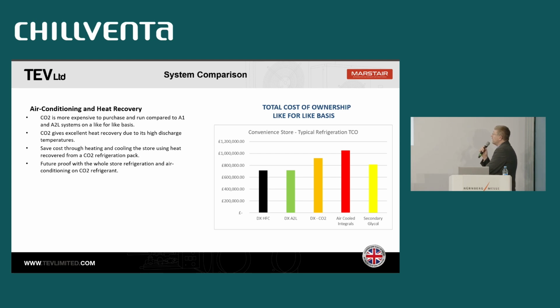So in terms of what I'm talking about, it's air conditioning and heat recovery on CO2. Our cassettes are mostly used with packs for supermarket applications. And generally at the moment, in a direct comparison with normal A1 refrigerants or A2L refrigerants, you tend to find that CO2 is more expensive, purely because of the pressures that you're working with, the cost of the kit and just how complicated it is. So if you can improve the efficiency of the system, and by that I mean recovering the heat for air conditioning or doing the air conditioning and the refrigeration all in the one system, then you can do a lot in terms of making the CO2 much more cost efficient, as it were.